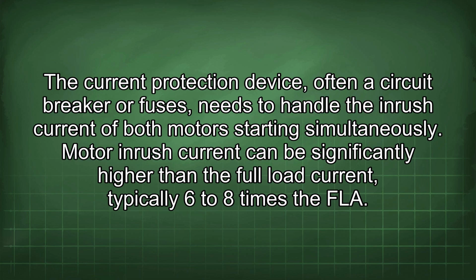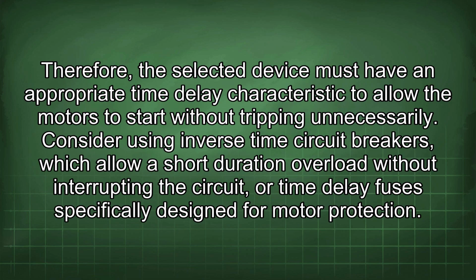simultaneously. Motor inrush current can be significantly higher than the full load current, typically 6 to 8 times the FLA. Therefore, the selected device must have an appropriate time delay characteristic to allow the motors to start without tripping unnecessarily. Consider using inverse time circuit breakers, which allow a short duration overload without interrupting the circuit, or time delay fuses specifically designed for motor protection.